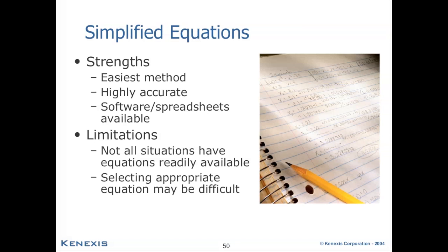Lastly, we have simplified equations, which provide the easiest method and a highly accurate method of solving fault propagation modeling. And software and spreadsheets may be available for these equations. But the limitations of this method are that not all situations have an equation that fits the situation, or sometimes selecting the appropriate equation may be difficult due to multiple equations being available for a given situation.